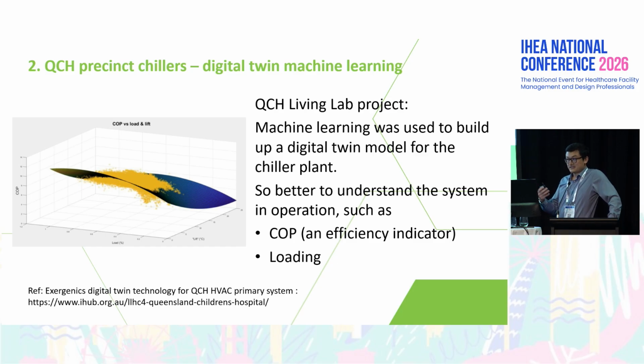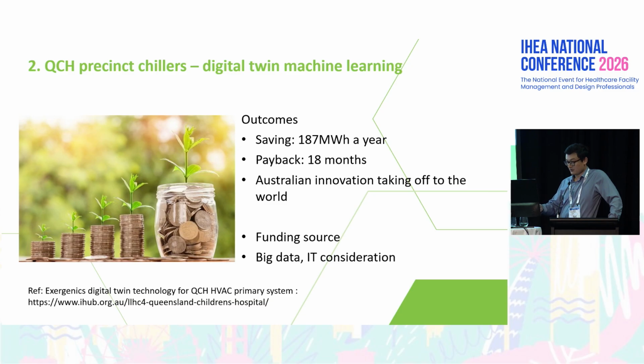With this digital twin model, we simulated hundreds of scenarios - different external temperatures, humidities, and our operation loading - then optimized the control logic for the chillers. Here's the outcome: we saved 187 megawatt hours of electricity a year, equivalent to 34 households in southeast Queensland, with a payback period of about 18 months.